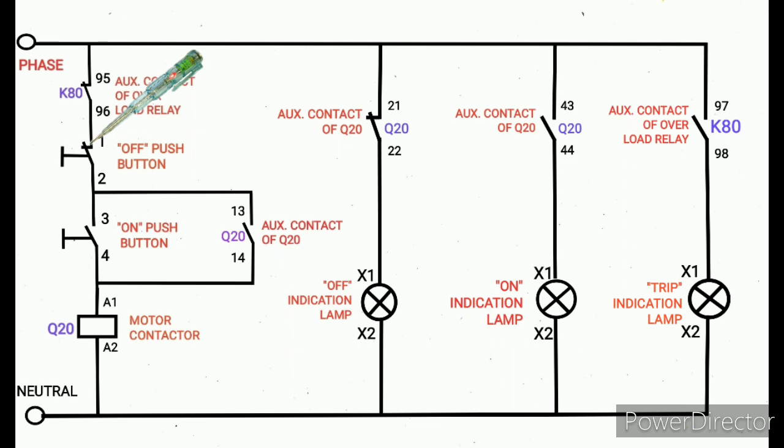Next, that off push button terminal number 1, we need to check. If the tester glows, okay, that line is okay. Next, that off push button terminal number 2 we need to check. Then it is okay. That NC off push button NC contact is okay.